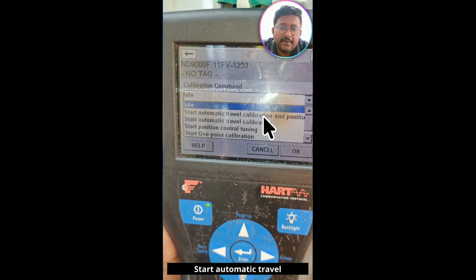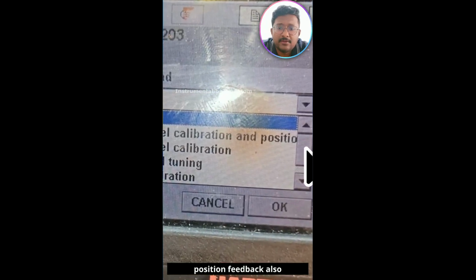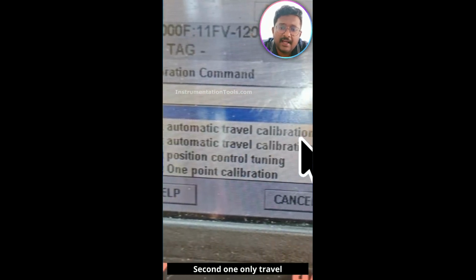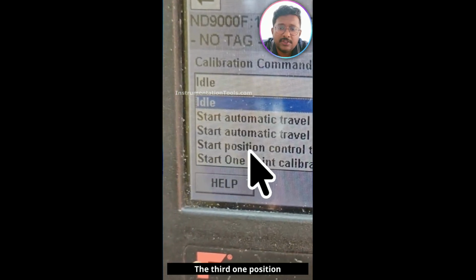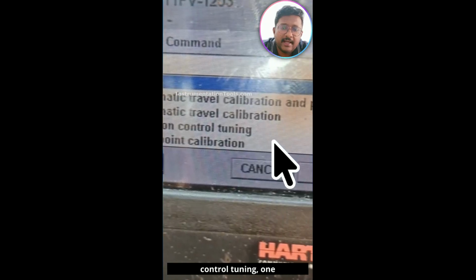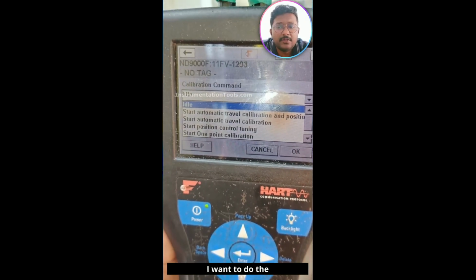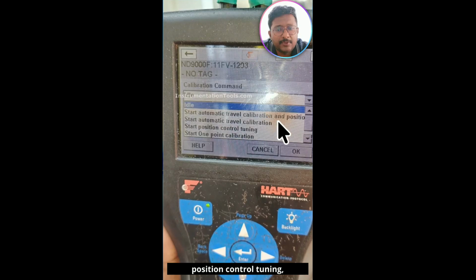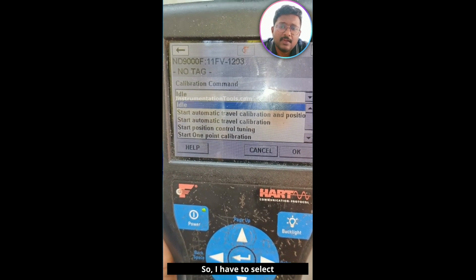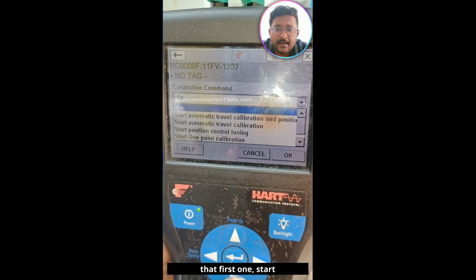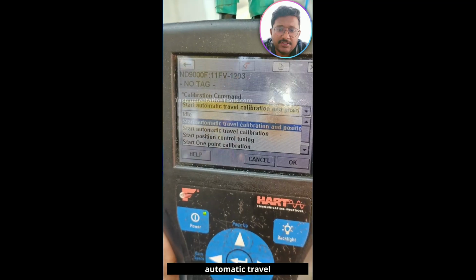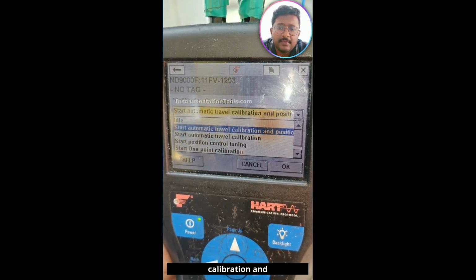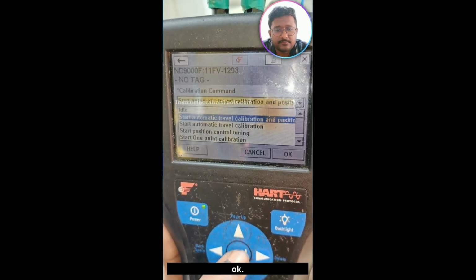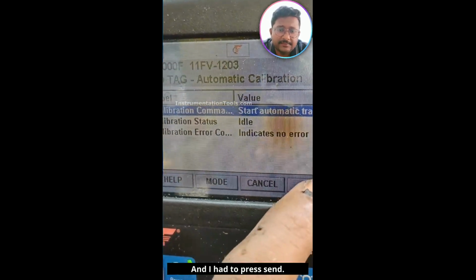Start automatic travel calibration and position feedback also included. Second one, only travel calibration. The third one, position control tuning, 1 point calibration, etc. I want to do the automatic travel calibration and position control tuning, so that calibration will be completed with feedback adjustment. Okay. So I had to select that first one, start automatic travel calibration and position, and then I had to press OK, and I had to press send.